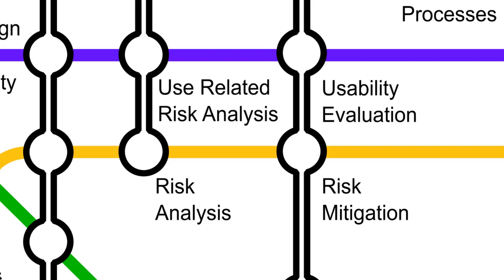These mitigations must be tested to see if they work and whether they introduce new risks or use errors into the device design. The results should feed back into design controls and human factors evaluation.